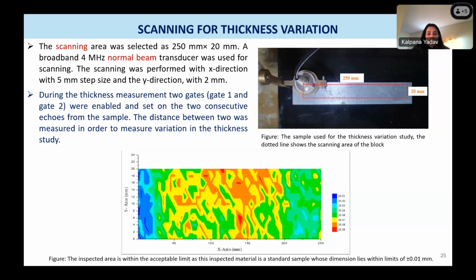So if you can correctly monitor your thickness, you can correctly monitor your ultrasonic velocity also by this method, and ultrasonic attenuation also. So you can see by just looking at that, and that thing is not possible with manual testing. I will say you cannot see the image, you can only have a number of measurements or something.